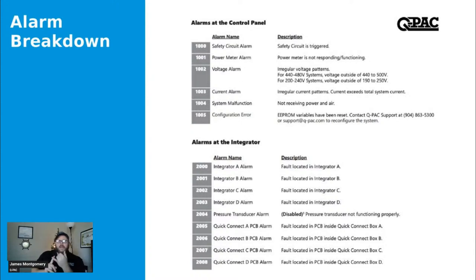The next few are related to the power meter. So 1001, 1002, 1003, and 1004 are all related to the power meter. We've got a power meter inside of our control panel that we pull the inlet power and we monitor it. So we're actually checking incoming power. And if it's not within 5% of the rated voltage for this device, then it's going to be an alarm. This is not a shutdown. So 1001 through 1004, actually we'll move on to 1005, is not a shutdown. You can have this alarm. It's more of a notification, right?